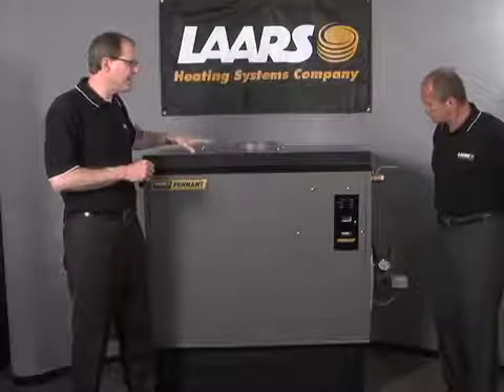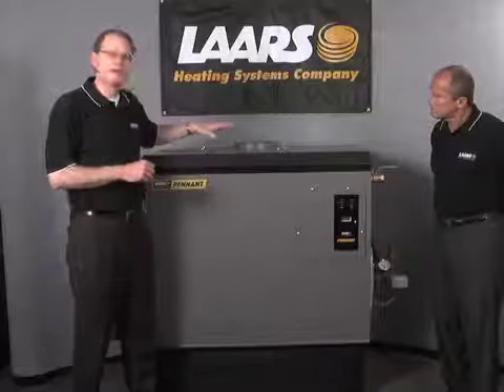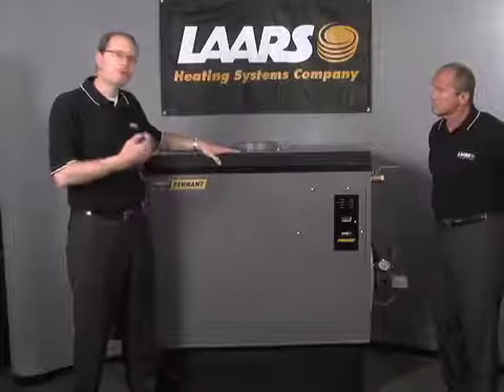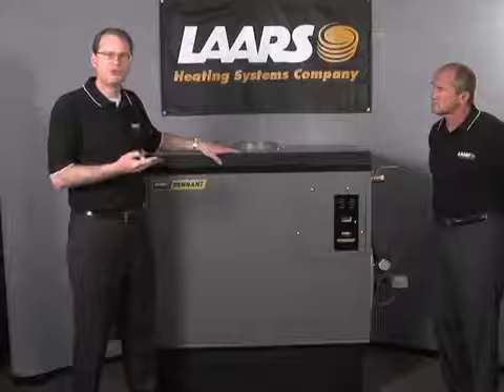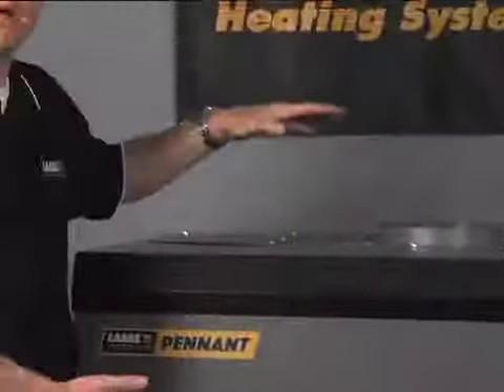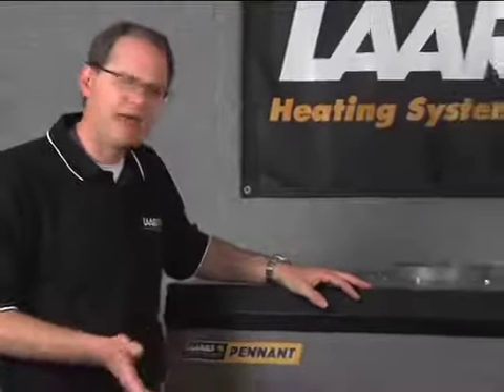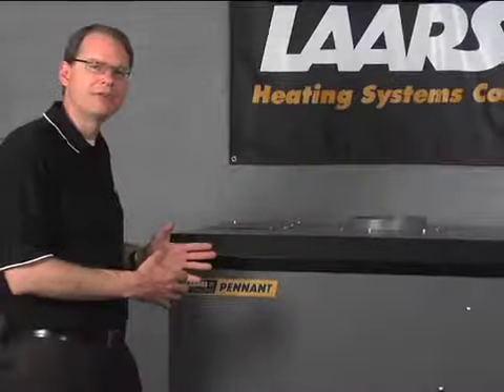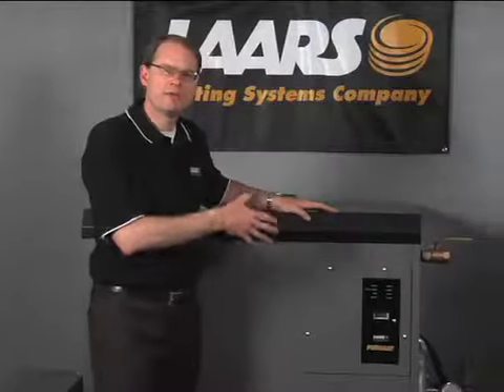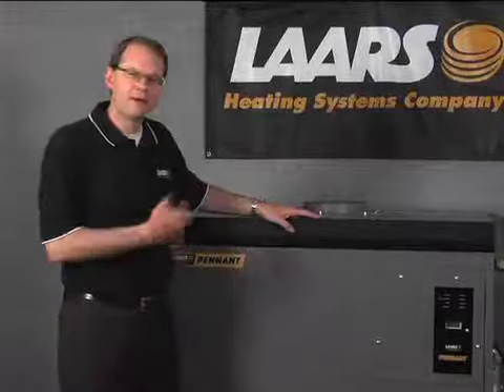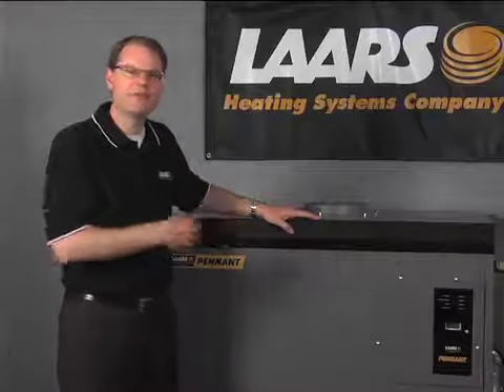The other nice feature that John had mentioned was that the Pennant is stackable. So you can put 4 million BTUs, that's 2 million BTU boilers, on a rack and have a really tight footprint, with the advantage of reversible water connections. And Laars is the only manufacturer in the industry that in fact uses flanged water connections to the boiler heat exchanger. So if you needed to isolate the boiler from the system piping, Laars does include for you flanged water connections, so it's easy to disconnect the boiler.